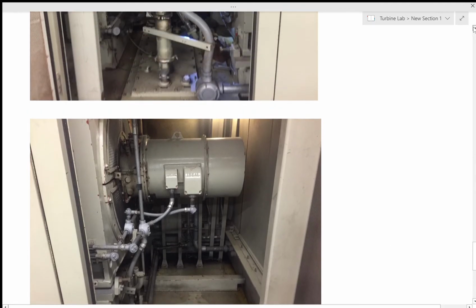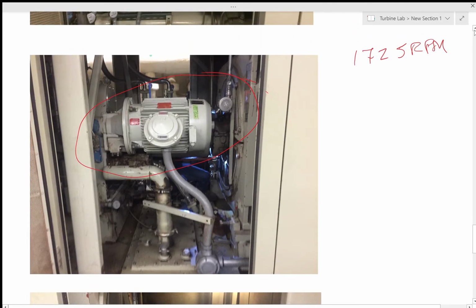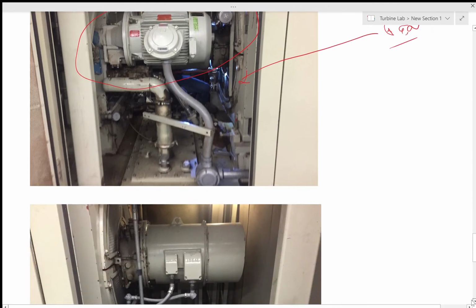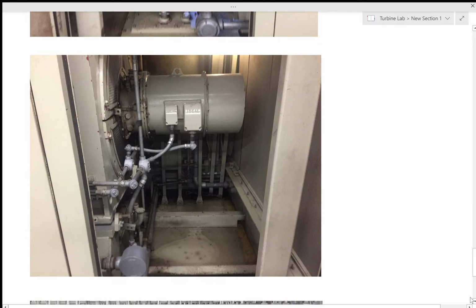Let's see, can we see it? Yeah. Right here is the generator. The generator part of the turbine starts right there, and it goes about another, I'd say probably 10 feet. And this is the back side of the generator. And this is where we have two things on here. We put the DC current in onto a set of slip rings, and then we also have our voltage control, the voltage regulator. And this is where we put the field current onto the slip rings.